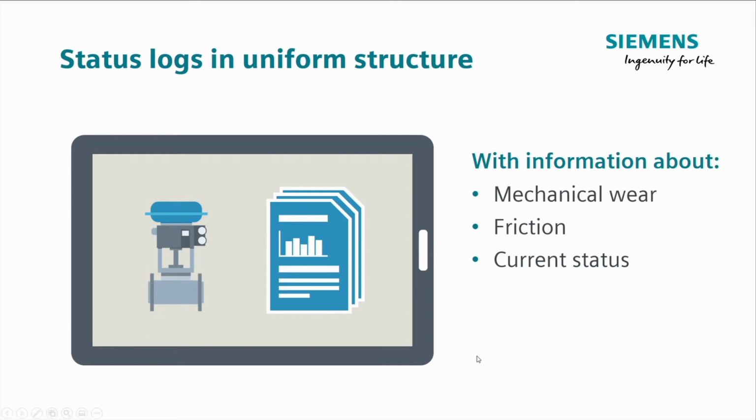We also look at things like stiction. So say if you've got a ball valve, it might be sticking at certain places, and you're not seeing that, apart from when you try and do PID, you're finding that your PID is struggling around certain positions, so the product or your quality might be affected. So it can monitor that. And because of the way it works, which you'll see in a minute, we can monitor for air leakage.